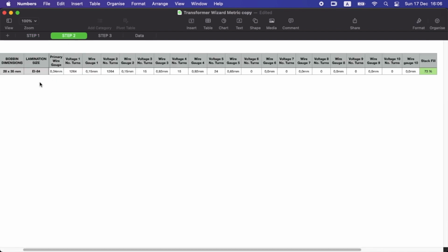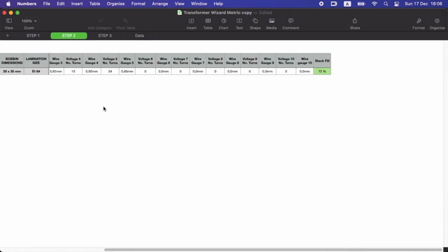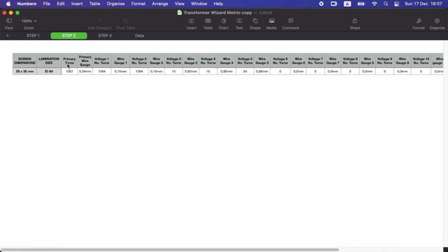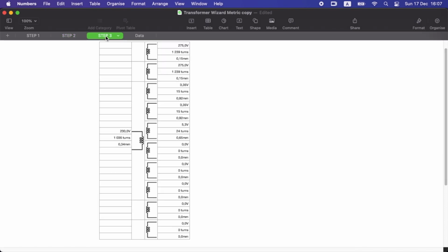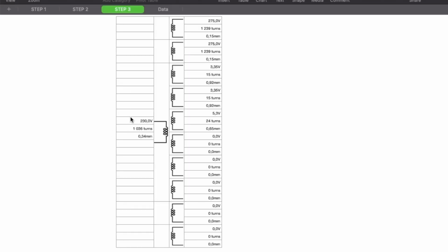You can see that the wizard found the perfect optimal lamination size and bobbin size, and calculated the number of turns for each and every winding along with the wire thickness. And it made sure that the combination of all those wire gauges and numbers of turns fits the bobbin perfectly. The Imperial version calculates everything in inches and for Imperial standard dimensions of laminations, and also the wire gauges in AWG standard numbers. Sometimes you might get more possible options or answers.